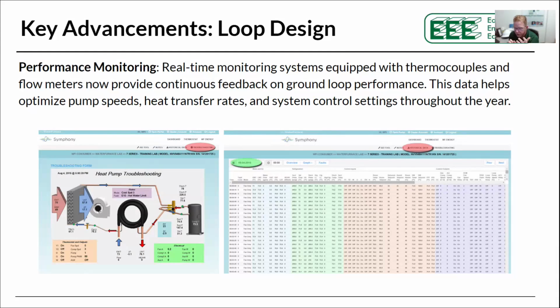You can see everything from ground loop flow, entering water, pressure drops, refrigerant data, heat of extraction, air temperature into the space—there's literally nothing you can't see as part of that. It allows you to provide performance monitoring for the building owner, whether commercial or residential, and gives you the opportunity to validate your data. Did we do a good job? Is there something we should be doing on the next one? If we did testing up front, is the real-time data matching the testing?